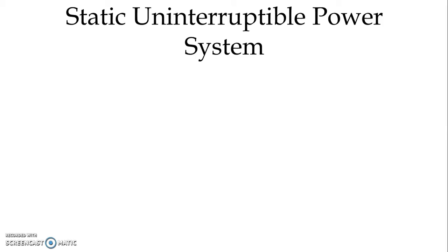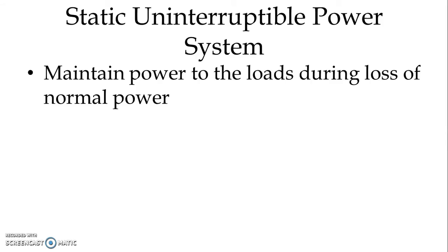In case of low frequency or power frequency disturbances, if there is a total loss of power supply from the utility or some of the values falls below the predetermined value, then we can use our static uninterruptible power system. We use a static UPS to maintain power to the critical loads during total loss of the normal power, or as I said, during certain values which falls below predetermined values.